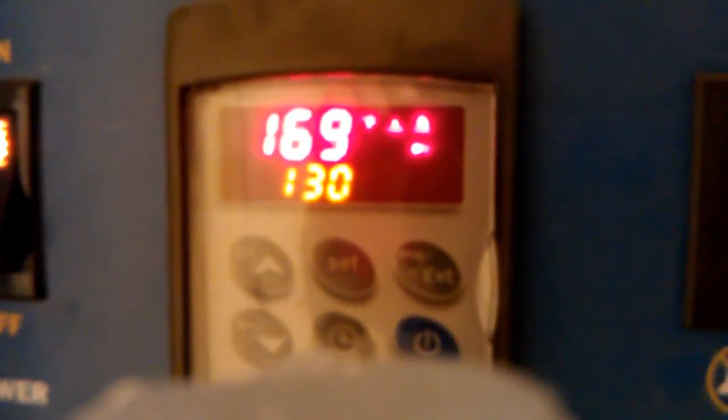Now we're approaching our normal heat rise at about 40 degrees, measuring from the inlet water temperature sensor to the outlet.